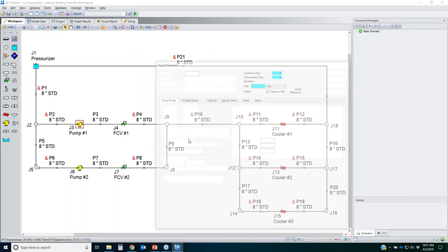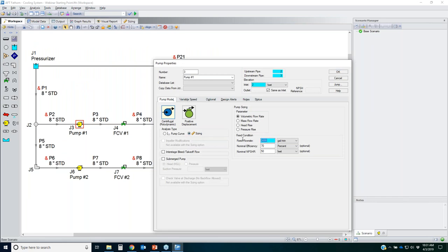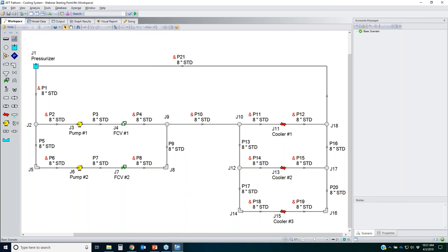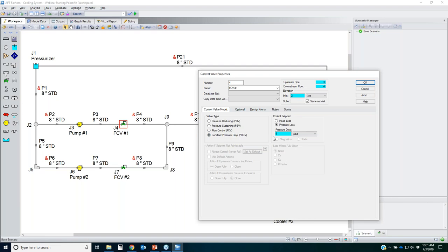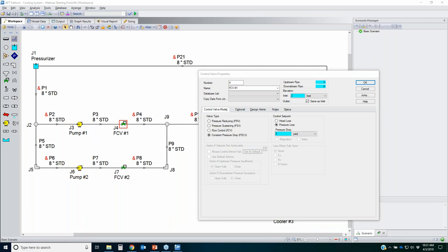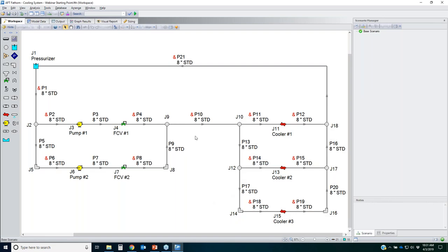Regarding the pumps: they are set to the sizing option with a fixed flow rate of 3,000 gallons per minute, nominal efficiency of 70%, and nominal NPSH required of 50 feet. I need to ensure NPSH available is well above that—this will be a design requirement. The control valves are set to constant pressure drop at a minimum of 5 PSI. Once I have pump curves, the control valves can become flow control valves.